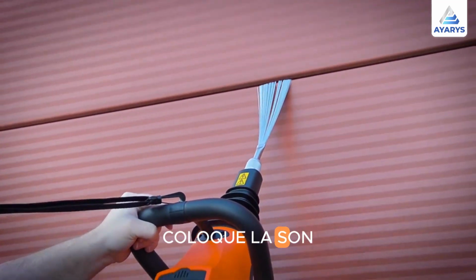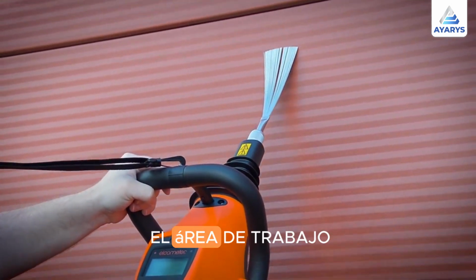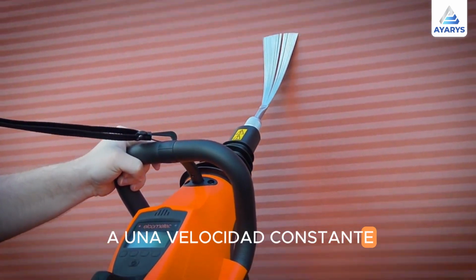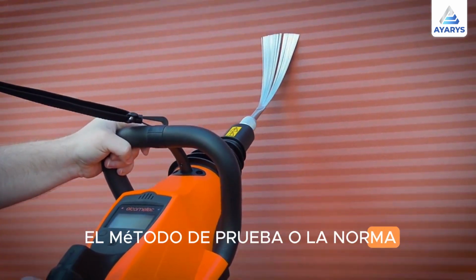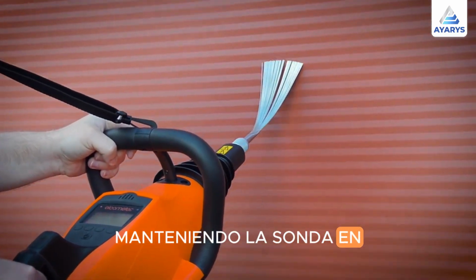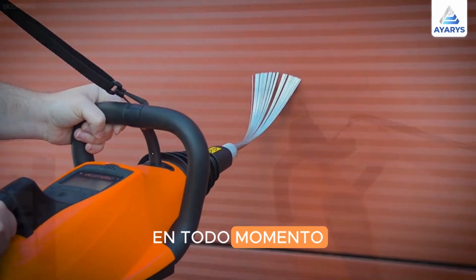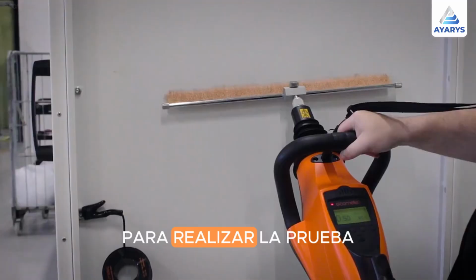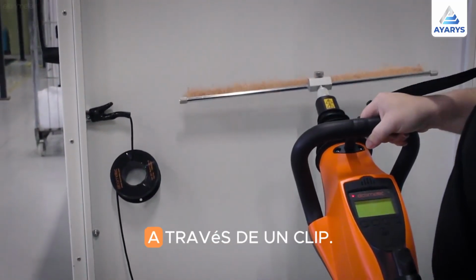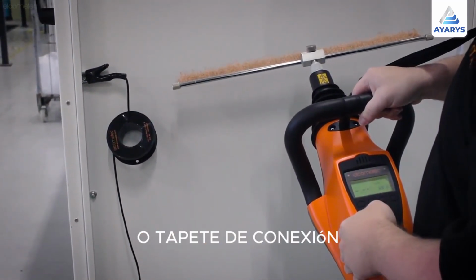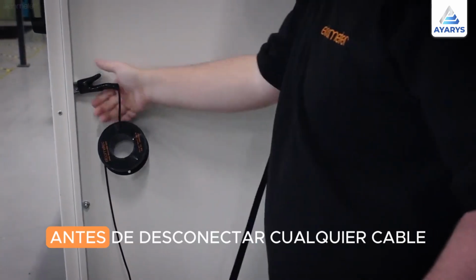Place the live probe on the test surface and move it over the work area at a constant speed, as defined by the test method or standard you're working to, keeping the probe in contact with the surface at all times. If you need to move to a new location to test, and you're connected to the substrate via a clip or grounding mat, always switch off the instrument before disconnecting any cables.